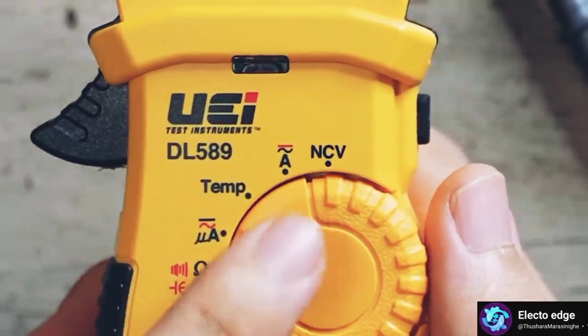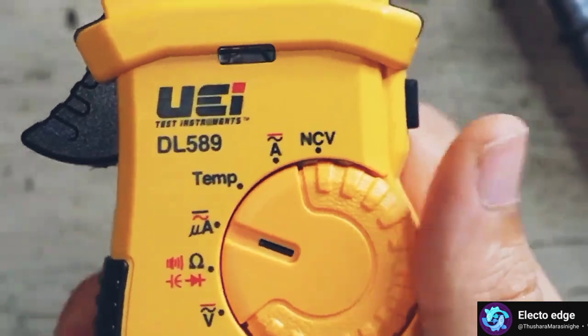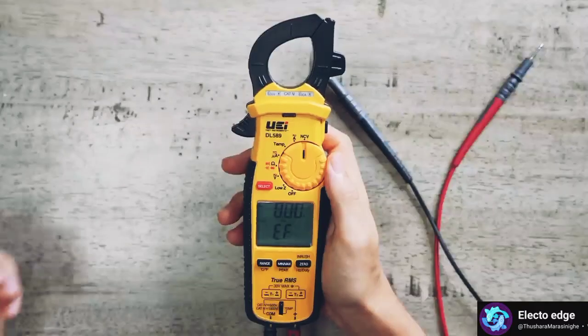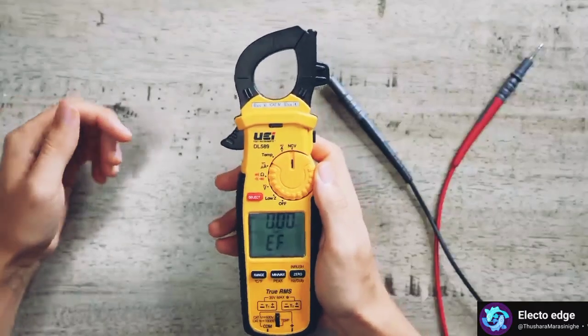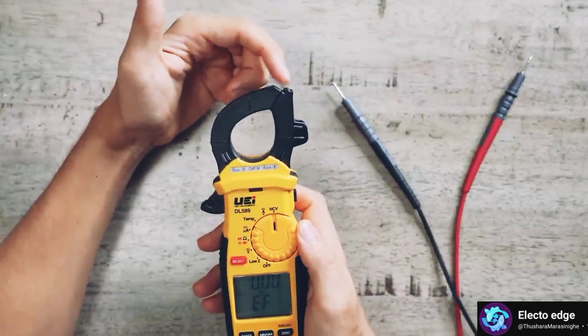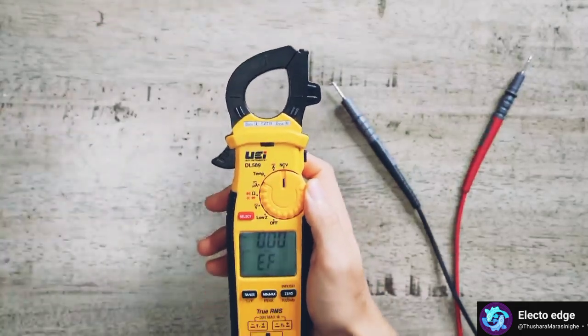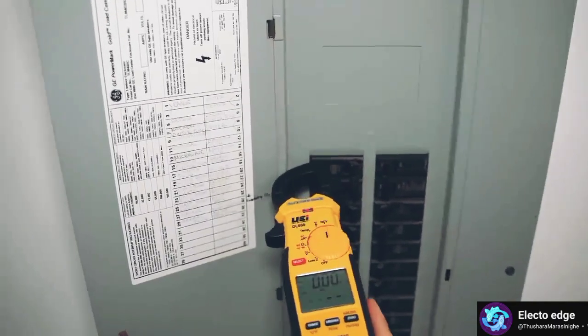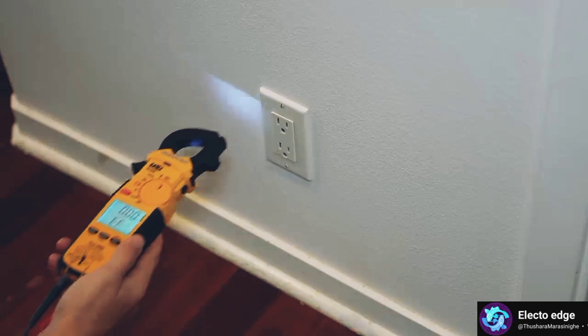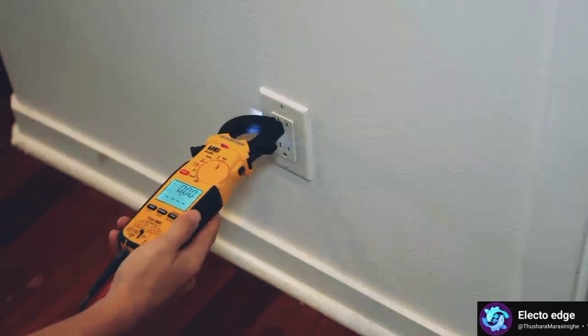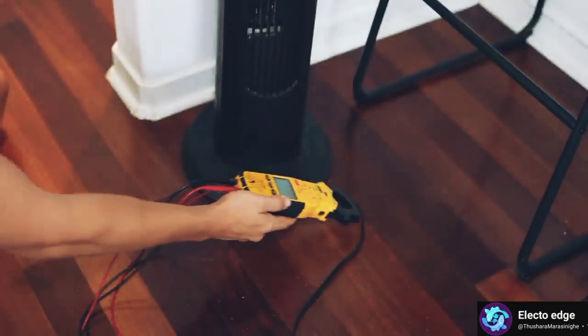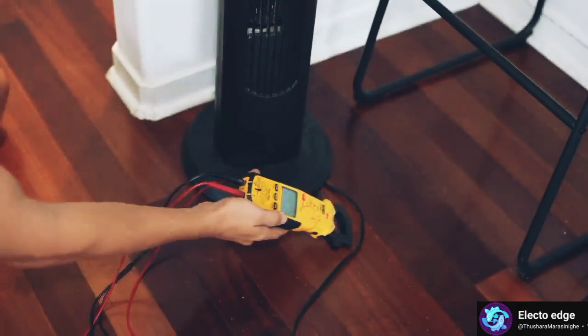Next up, we have non-contact voltage, labeled as NCV. With your meter set to non-contact voltage, you could use the tip of the clamp as a voltage pen to detect if there's any power in the area. It's a fast and easy way to check if there's any power at an outlet, a light switch, or if a power cord is energized.